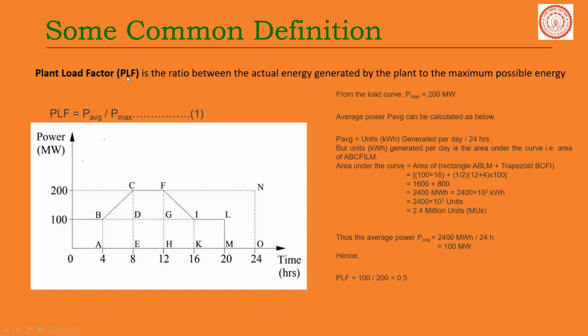So how do we calculate the plant load factor? It is the ratio between the actual energy generated by the plant to the maximum possible energy. Here the maximum possible is 200 megawatt, and we look at how much energy was actually produced over the day. Actual production divided by maximum possible production gives the plant load factor. The maximum value it can reach is 1, when the numerator and denominator are equal.